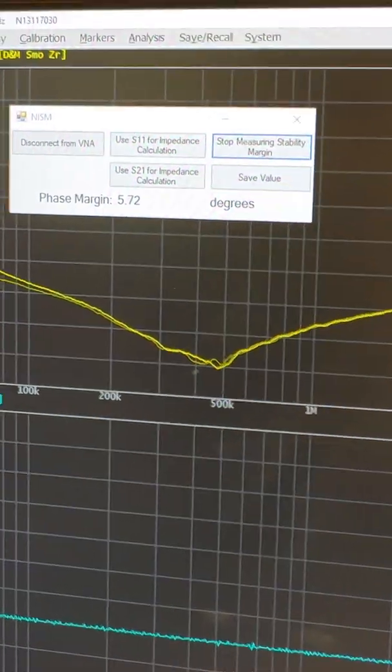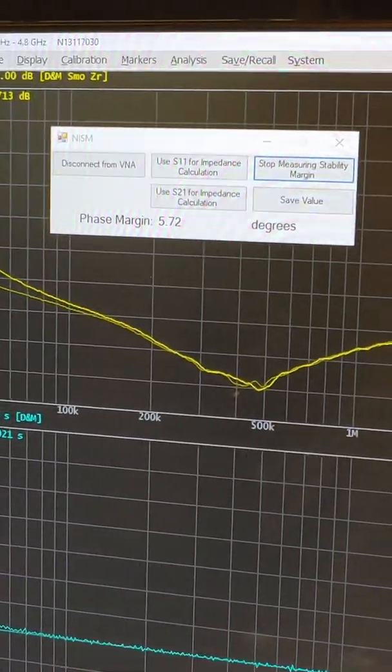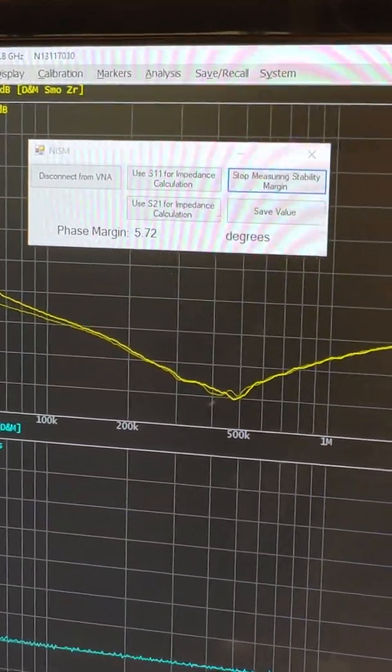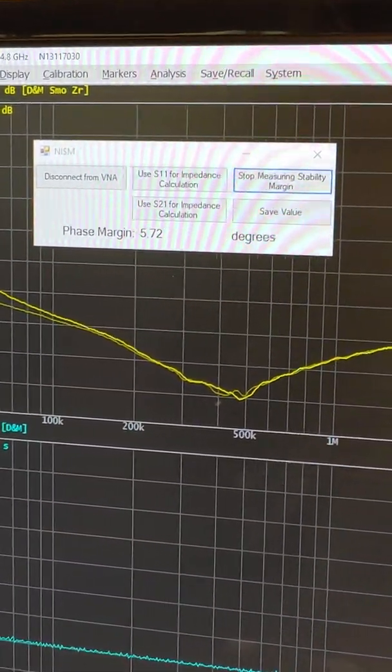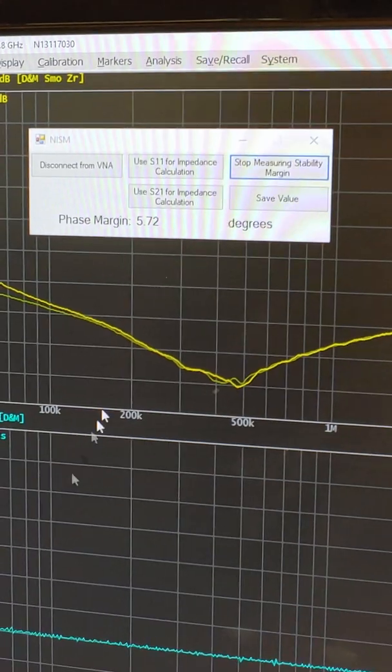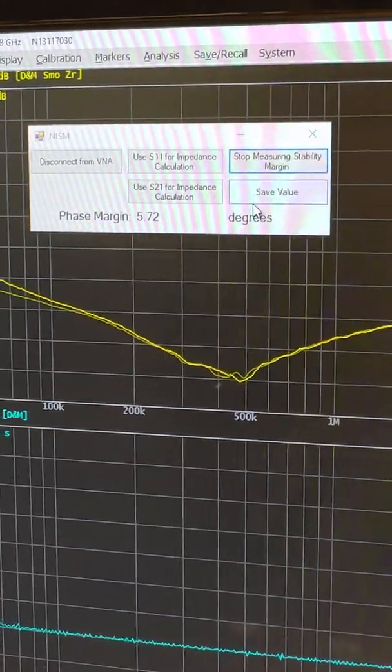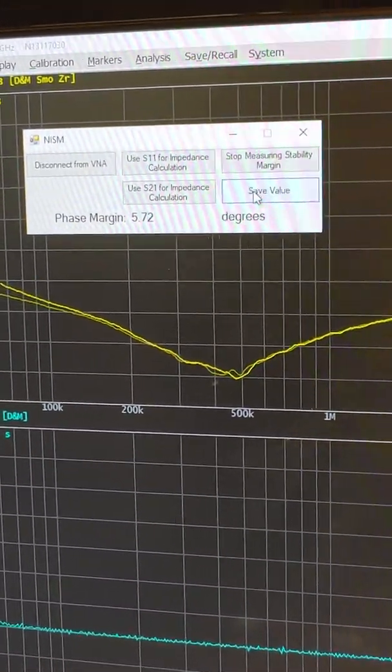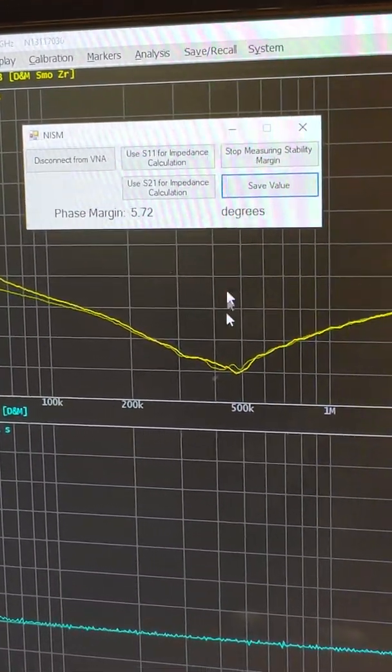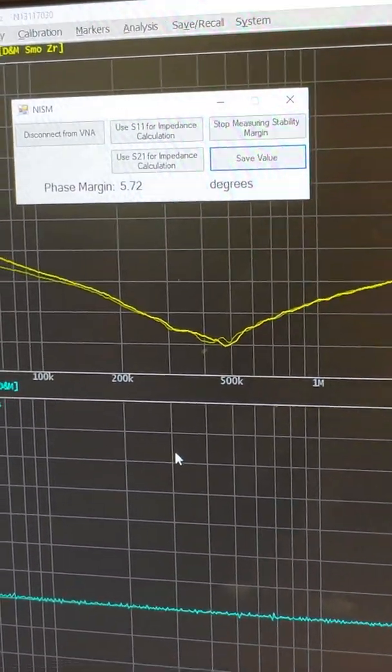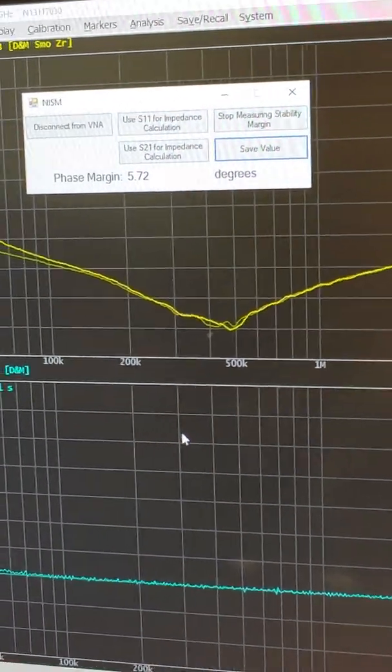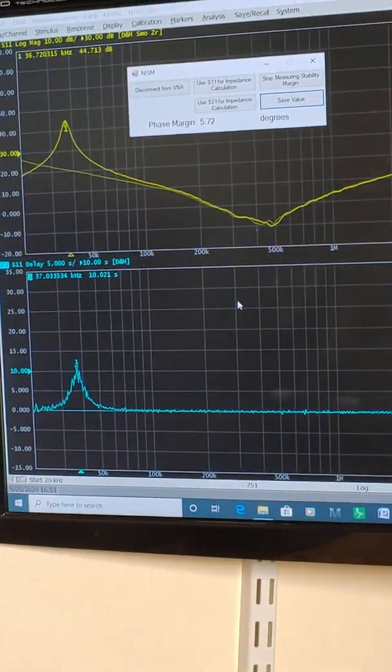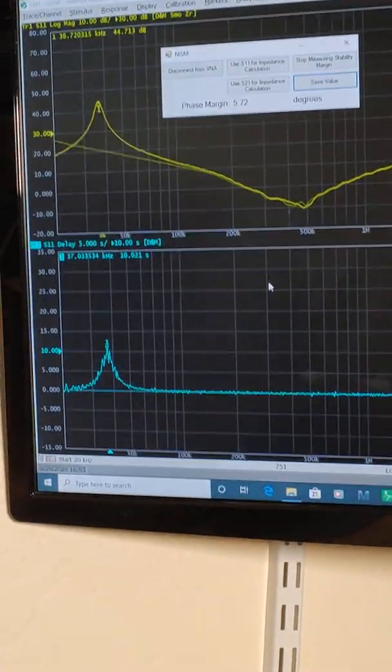That tells us that the phase margin of this folded reference with ceramic caps is 5.7 degrees. If you want to save that value, we can save it to a text file. Just click Save Value, and we're done. That's how simple it is to do the one-port NISM impedance with the Copper Mountain analyzer.